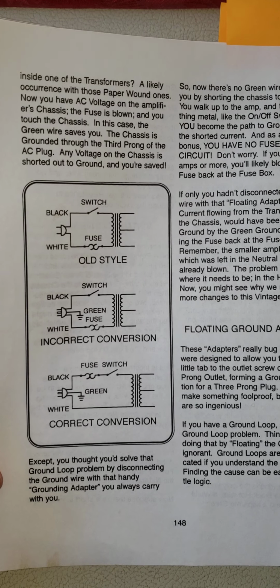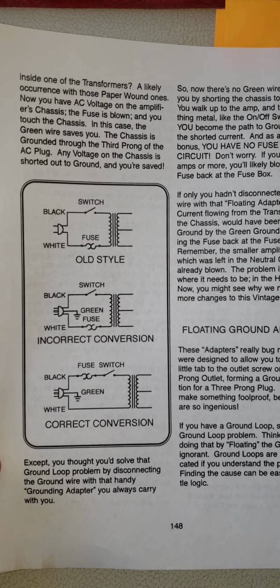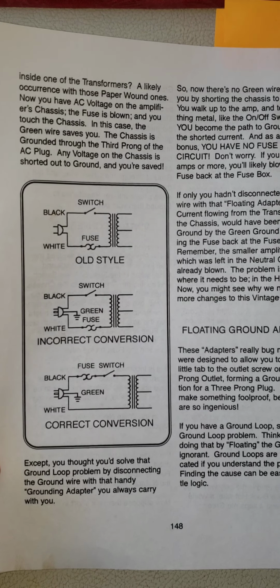Notice it shows the old style where oftentimes the switch was on one leg, the fuse was on the other, and when you convert it, you want the green to go directly to ground, and you want the fuse to be the first thing that the hot line sees and the switch after it, and the neutral should go directly to the other leg of the transformer.